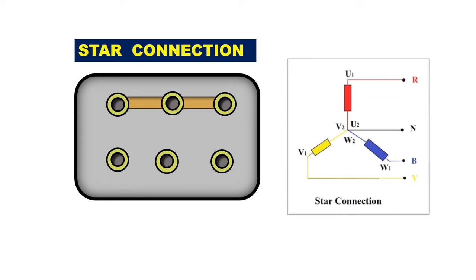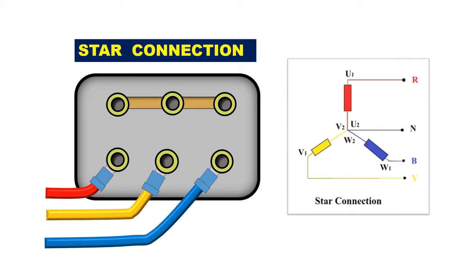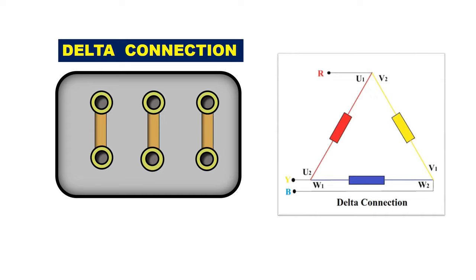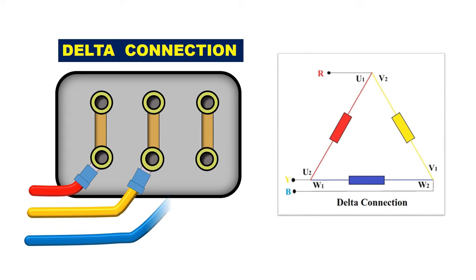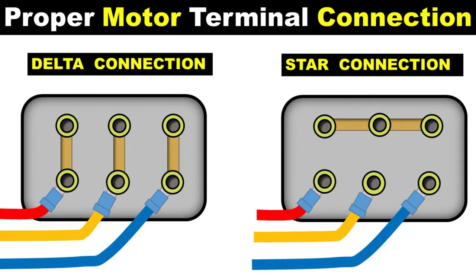If motor connection is done in star, then what you only need to do is connect R, Y, B — all three phase power supply — to the below three terminals. If motor windings are connected in delta, then by connecting power supply to motor to run it, take all the R, Y, B phase power supply and connect to the motor terminals like this. You can see here how to connect the wires in this connection.